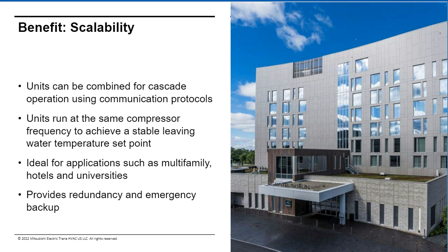The average commercial heat pump water heater is around 10 tons in capacity, which, depending upon climate, is suitable to serve 40 to 70 apartments, hotel rooms, and so on. It varies with the climate and other factors such as storage sizing and storage temperature. If an application requires more capacity, you simply add more modules to scale capacity at the heat pump water heater domestic hot water plant, and you also have to increase the size of your storage in lockstep.